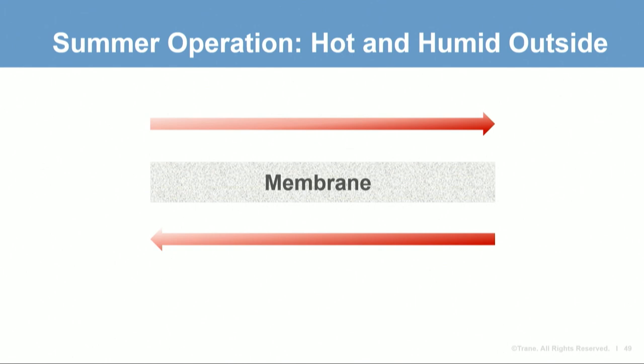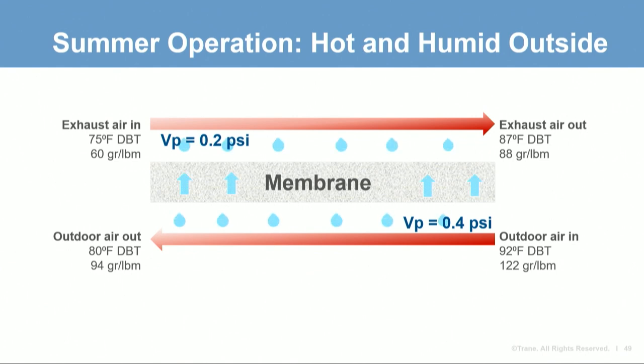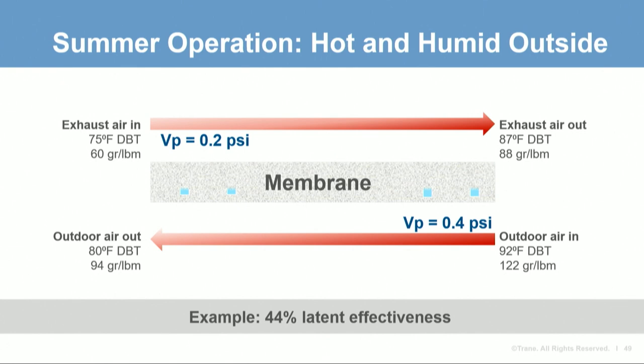Looking at a summer cooling example: the entering outdoor air is 92°F and 122 grains of water vapor per pound of air, with a water vapor pressure of 0.4 PSI. This pressure differential is the force that transmits the water vapor molecules through the solid membrane material. This example has a 44% latent effectiveness at these conditions, assuming equal air flows.